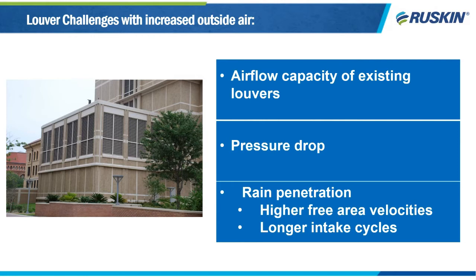On large banks of louvers with plenums behind them, is the plenum designed in a way that will allow more airflow through it? All of this can create high pressure drop through the louver that is too great to allow more airflow without increasing your fan power. And for both existing and new designs, more airflow means greater potential for water, either by higher intake or longer intake periods.